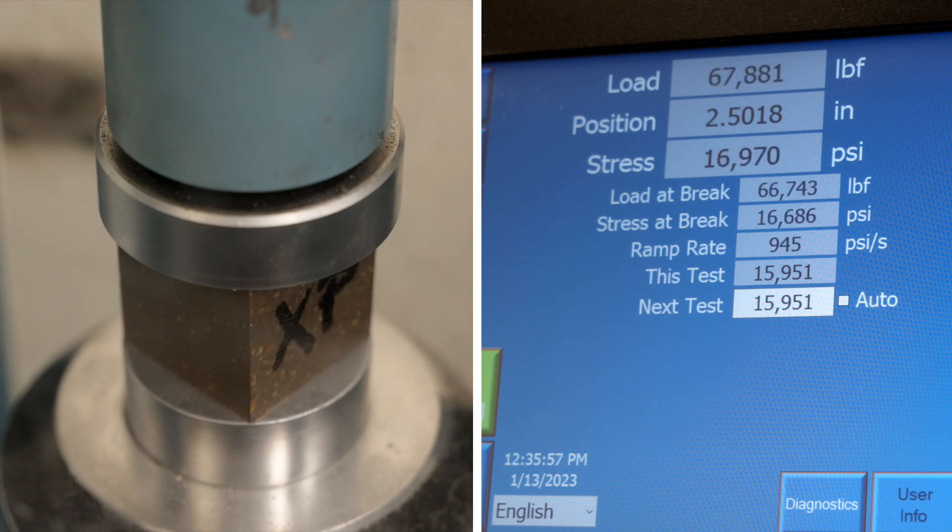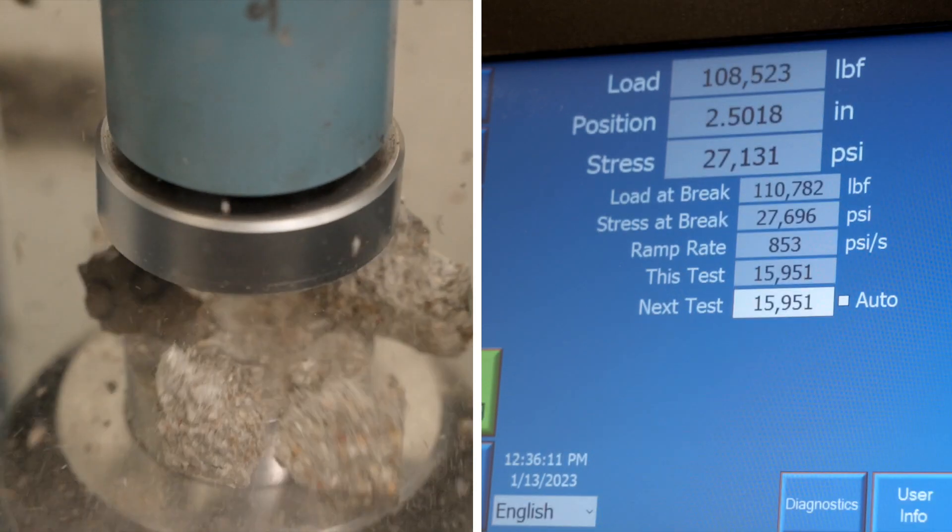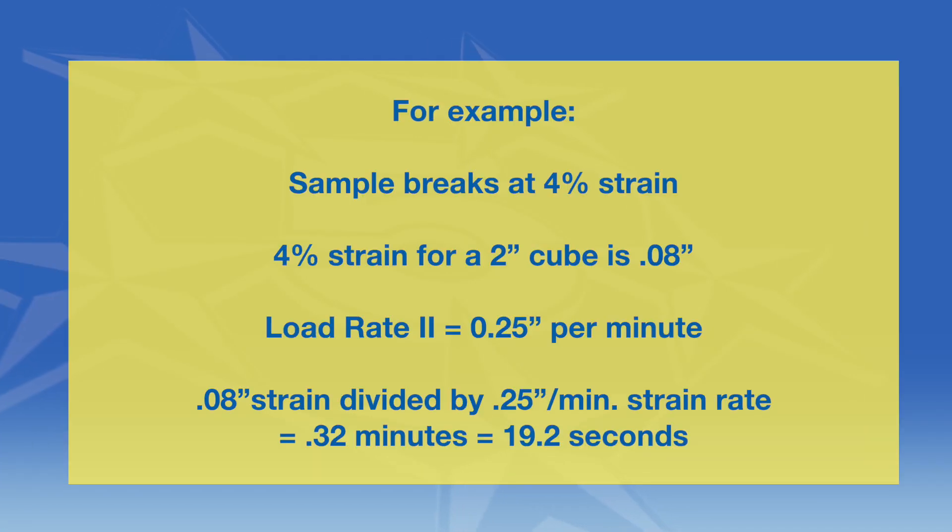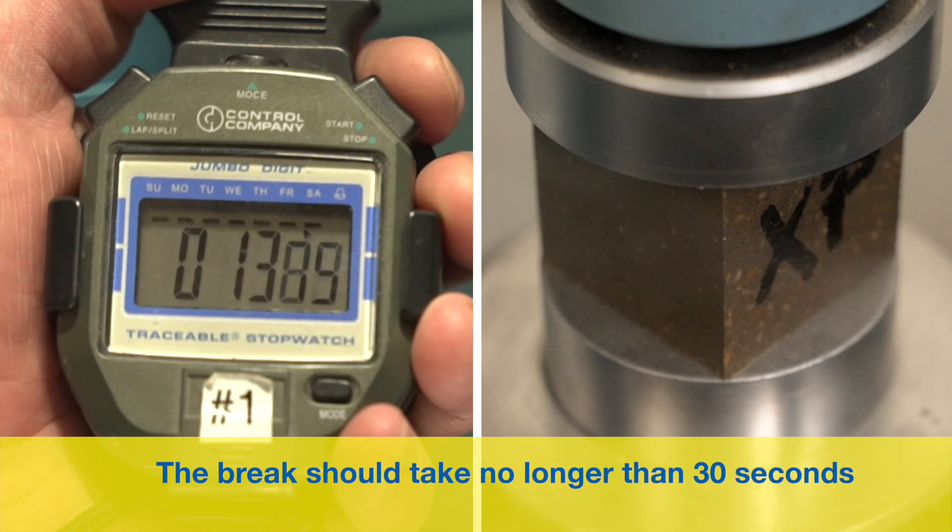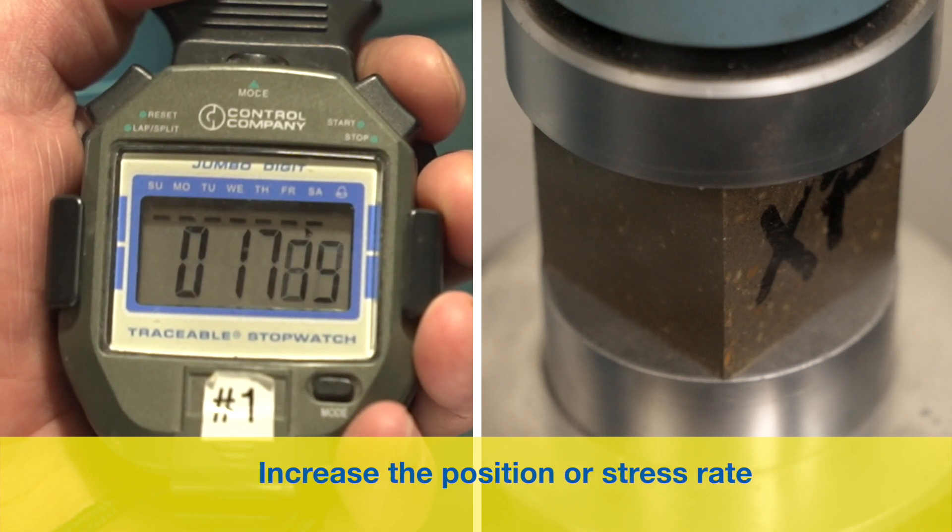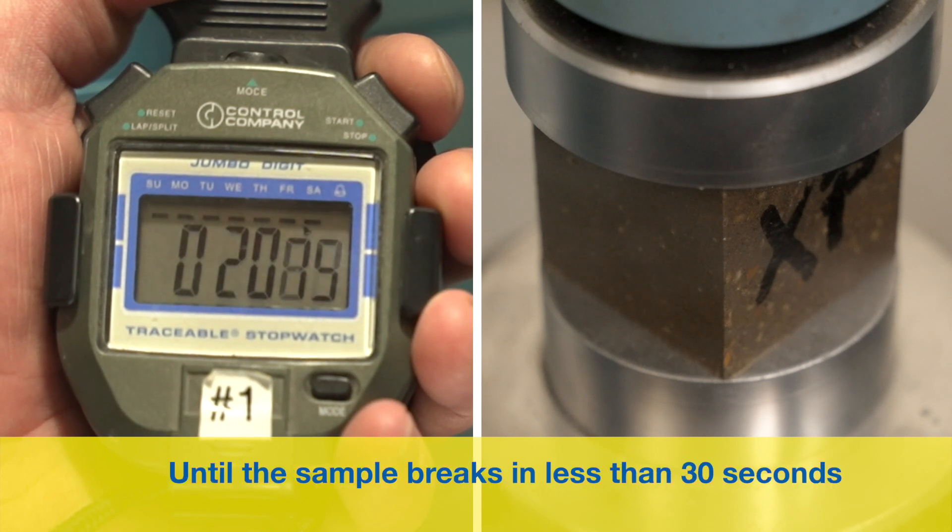Fortunately, there is a relatively easy way to determine this. 5-star epoxy grouts typically break at between a 4 and 6 percent strain. When the machine runs in the loaded state at load rate 2, the material typically takes 20 to 30 seconds to break. This expected time to break is calculated as follows: 4 percent strain on a 2-inch cube equals 0.08 inches. If the test machine's actual position rate while loaded is the prescribed 0.25 inches per minute, the machine head will travel that 0.08 inches in 19.2 seconds. At a 6 percent strain to break, the sample will take 29 seconds to break. Therefore, if the sample takes longer than 30 seconds to break, there is likely an issue with the position rate of the compressive testing machine running in its loaded state. Increase the position or stress rate until the sample breaks in less than 30 seconds.